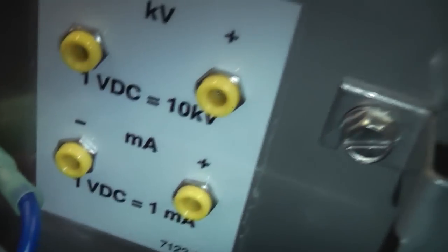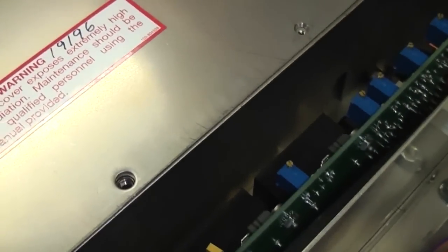The coils are secured down with these sort of security-ish screws, but that's no major issue. On the side here there are some monitoring outputs, so you've got 1 volt per 10 kilovolts and the tube current 1 volt per milliamp outputs for testing. I'd imagine everything inside this enclosure is probably made by the X-ray tube manufacturer as a sort of custom version for Faxitron to then use in their system.